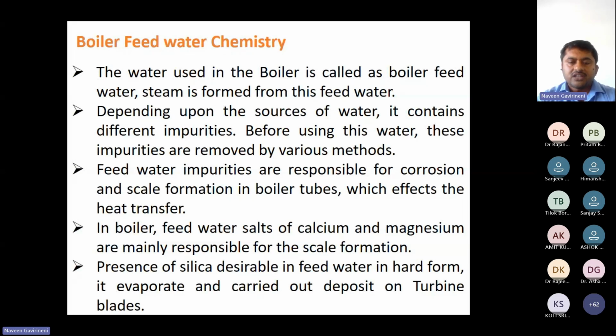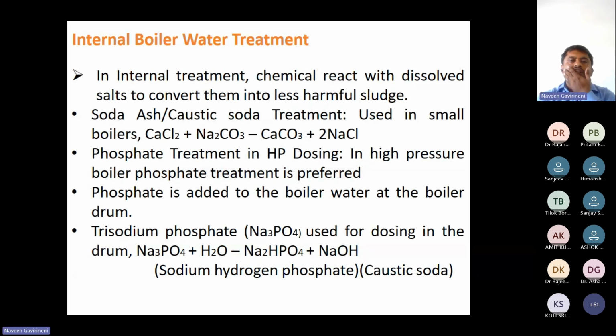Why silica? It is not soluble in water. It transfers to the steam and deposits on the turbine blades. Due to deposition on the turbine blades there is an imbalance, and there is a chance of increased vibration, which finally damages the turbine. So there are two types of treatments: one is internal and the other is external. Internal treatment uses soda ash and caustic soda.